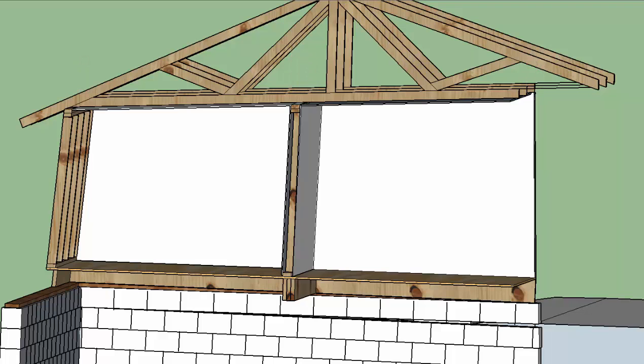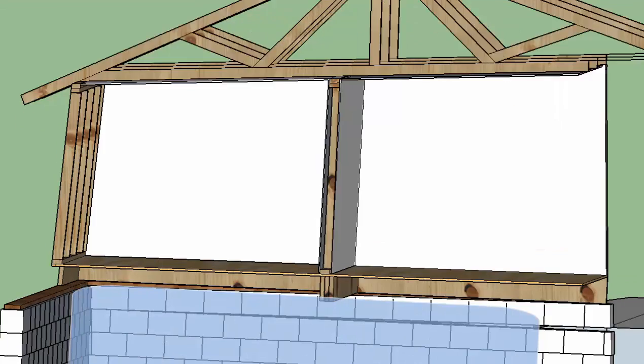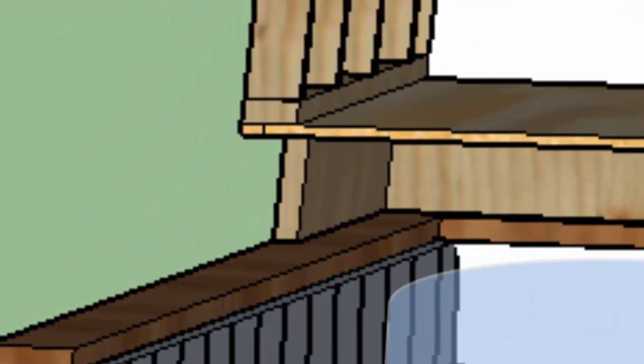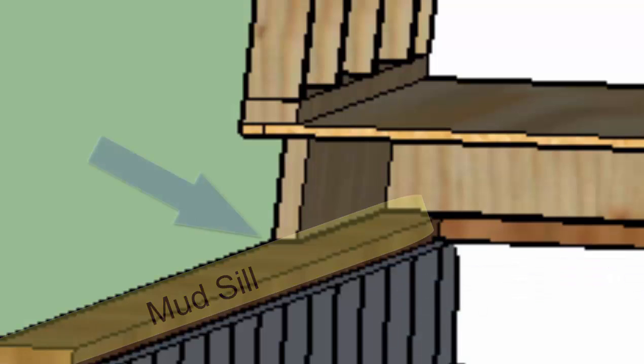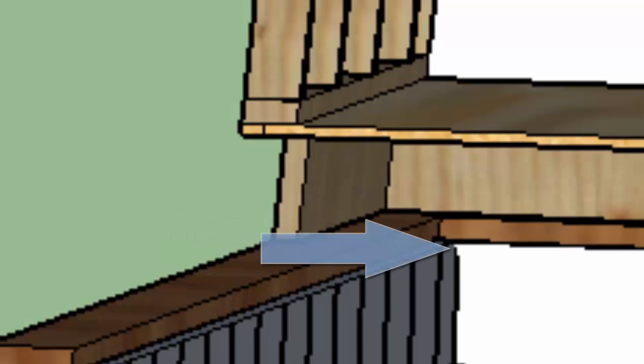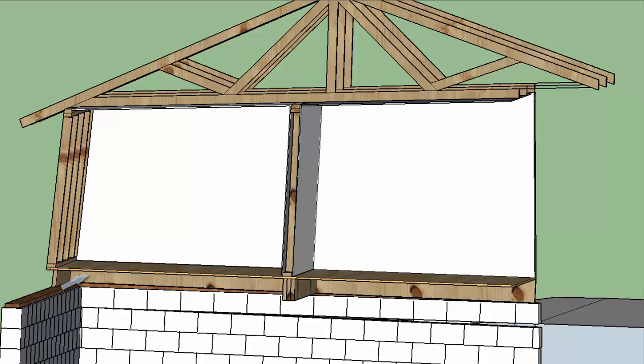The air that is leaving the house through the small gaps in the ceiling creates a low pressure pocket in the lowest place in the house, which is in the basement. This happens along the perimeter joist and the mud sill at the top of the basement wall and other gaps and openings. Air infiltrates through these gaps to equalize the pressure, as nature loves balance. However, the air that enters through the gaps to re-pressurize the house is freezing cold from outside.